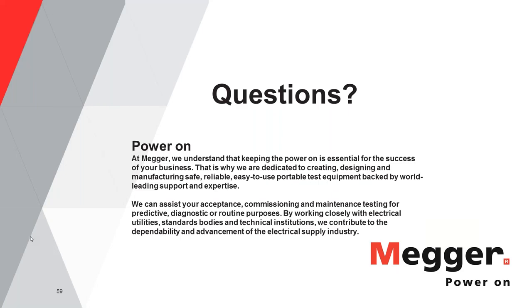All right. Our next question is, how are cables from the test set connected to the circuit breaker when the circuit breaker is installed? As shown in the presentation, connecting to the circuit breaker is one of the key points of the test. If you don't have a good connection, you will have a high impedance and that will make your test difficult, or you're not going to be able to test it. So you have to have short cables and a very good, tight connection.